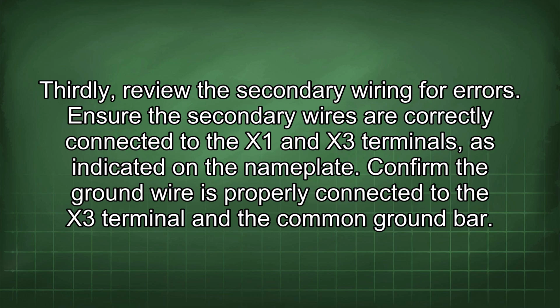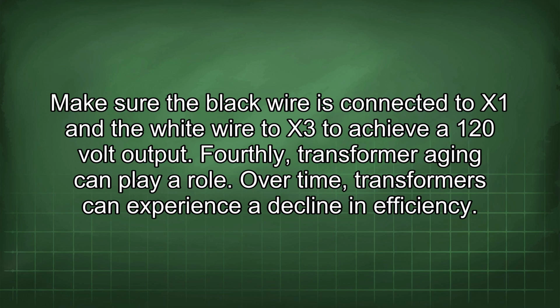Thirdly, review the secondary wiring for errors. Ensure the secondary wires are correctly connected to the X1 and X3 terminals as indicated in the nameplate. Confirm the ground wire is properly connected to the X3 terminal and the common ground bar. Make sure the black wire is connected to X1 and the white wire to X3 to achieve a 120 volt output. Fourthly, transformer aging can play a role.